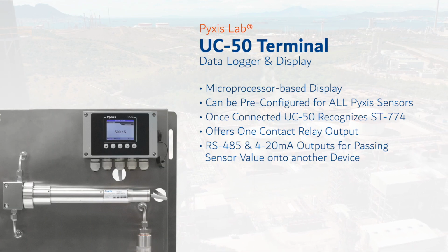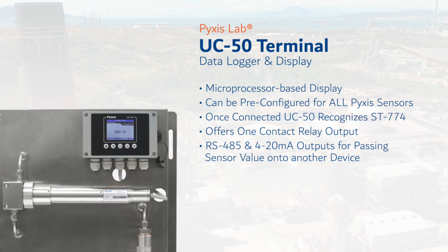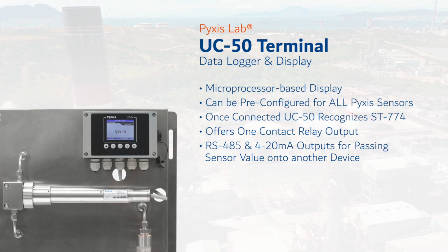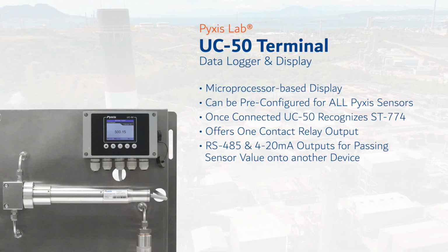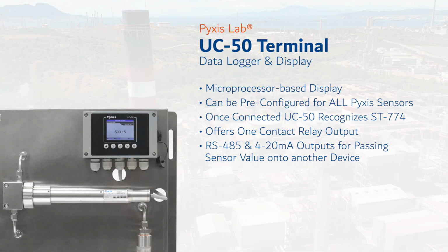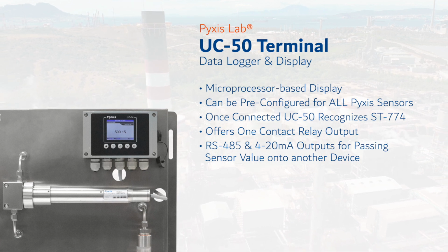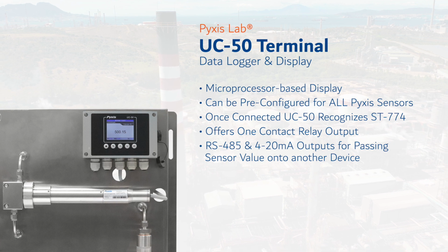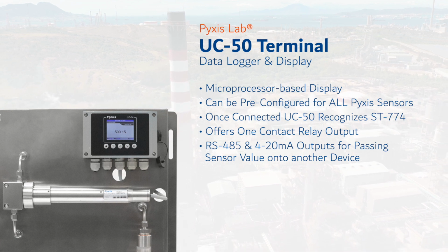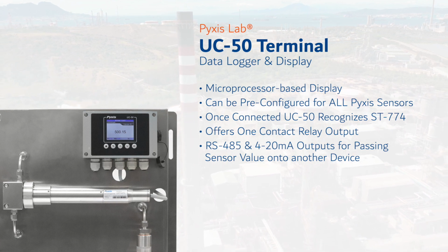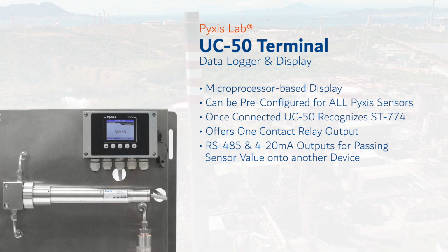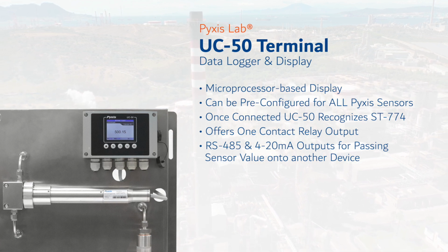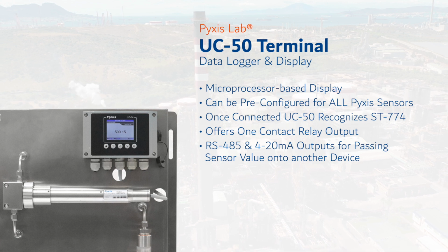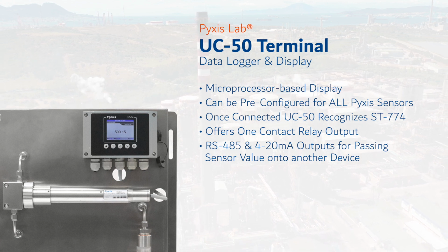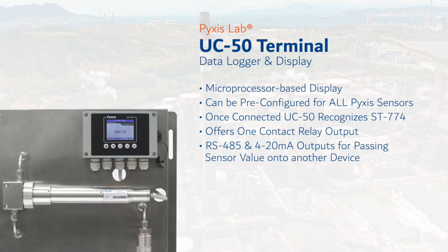As an added convenience, the user may purchase the optional UC50 display data logging terminal. The UC50 is a unique Pyxis microprocessor-based display and data logging terminal, which is pre-configured for all Pyxis inline sensors in an RS-485 Modbus format. Once the ST-774 is wired to the UC50, the display automatically recognizes the sensor and its configuration, providing immediate data display, data logging capability, and integrated calibration interface. UC50 offers one contact relay output and has RS-485 Modbus and 4 to 20 milliamp outputs for passing the sensor value onto another device.